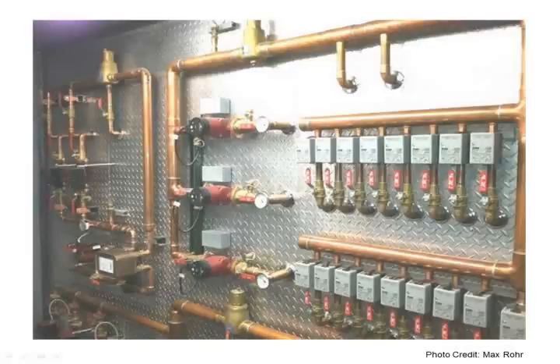What are those problems? Pump conflict. There's a couple of pumps over here. Hopefully you can see those okay. Those are meant to act independently of one another. If one pump turns on, it shouldn't affect the flow rate being driven by the other pump, and vice versa. They should be decoupled. So how do you apply the piping and design the piping to make sure you don't have pump conflict? And lastly, we can see some variable speed, electronically commutated motor type pumps over here, very efficient.